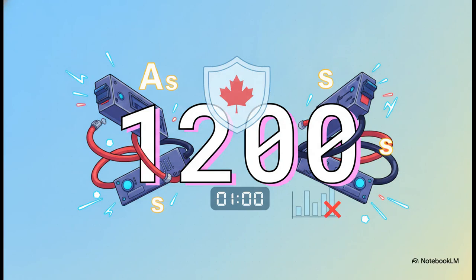1200. I want you to sear this number into your brain right now because it is a classic, textbook Red Seal trap. Under Rule 14-102 Sub-Rule 2, the absolute maximum setting for ground fault protection is 1200 amps. Plus, the maximum time delay is exactly 1 second for ground fault currents equal to or greater than 3000 amps. Seriously, don't let them trick you with higher numbers on the test. 1200 amps is the hard ceiling.